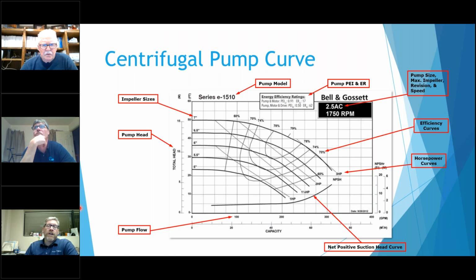But this efficiency rating can also take into account a motor and drive. A lot of times with these pumps, we can sell a drive with the pump, and so it's going to be paired with it. So you can see this efficiency rating actually goes down, where in fact the closer to 0 you are, the more efficient it's going to be. The higher the number, the less efficient. So you can see this 0.5 is quite a bit more efficient, by just putting a VFD on this pump, than the 0.91 with no VFD.